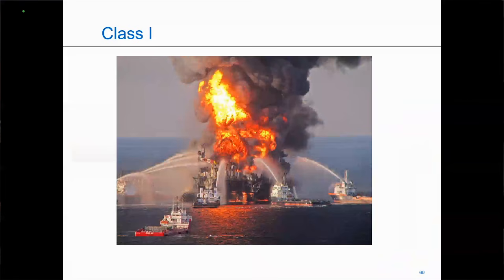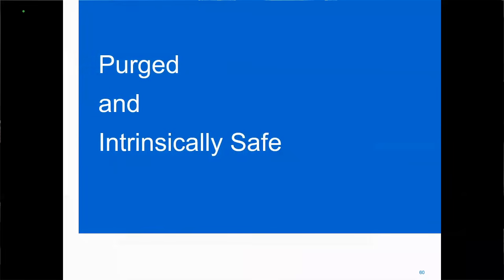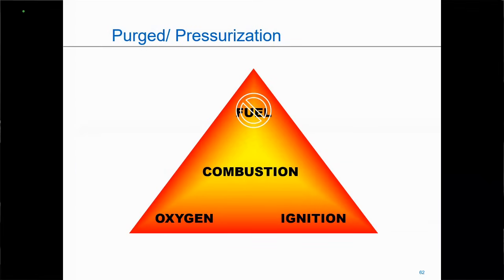When it comes to an area with NEMA 7 explosion-proof, we're looking to prevent this particular situation. Now, into the protection techniques of purged and pressurized and intrinsically safe: when I'm looking at purged and pressurized, I'm effectively removing the fuel leg of the ignition triangle. What I'm doing is putting an inert gas or air into the enclosure to make sure I can't have an oxygen and gas mixture.